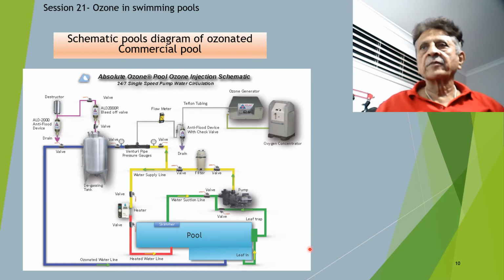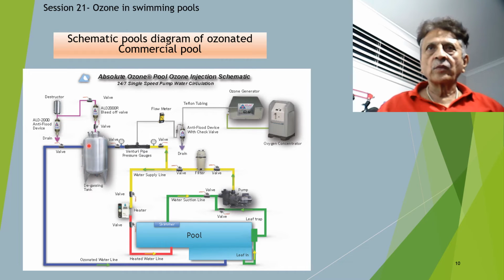This is a typical diagram of a commercial ozonated pool. This is a pool. Now, if you notice, there are 2 inlet lines where the water goes into the pool. There will be a skimmer line, which is a drain on the top of the surface of the side of the pool, which sucks out any water containing all the particles, etc. And you also have another suction line at the bottom of the pool that sucks the water onto the joints of the skimmer box, and together the water is sucked into the pump.